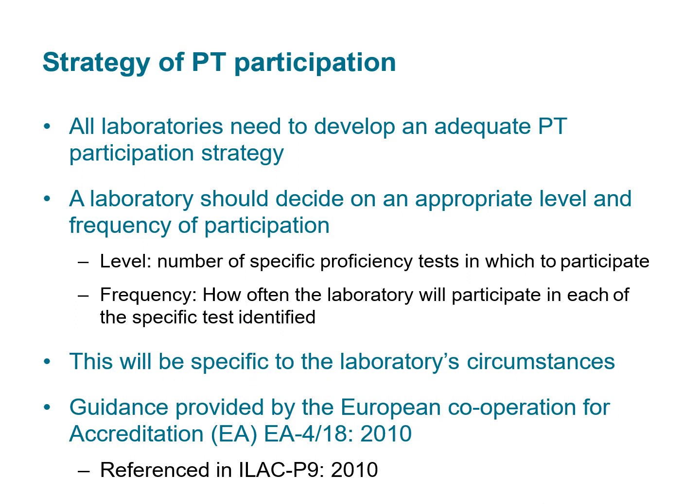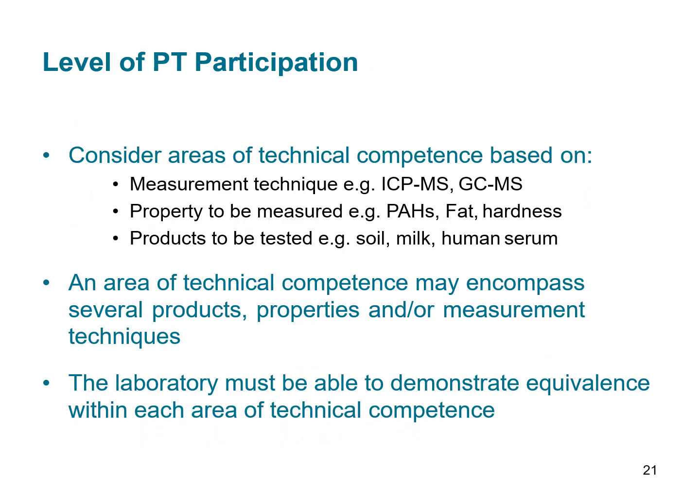So class, let's move on to the participation strategy to join the PT scheme. All the laboratories need to develop a proper PT strategy to join PT tests. Basically all the laboratories also have to decide an appropriate level and frequency of participation. Level is the number of specific proficiency tests in which to participate, and frequency is how often the laboratory will participate in each of the specific tests identified, and this is specific to the laboratory circumstances. The guidance provided by the European Cooperation for Accreditation can be followed in order to join the PT scheme.